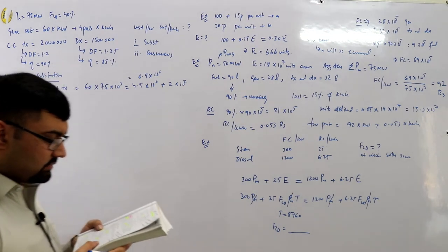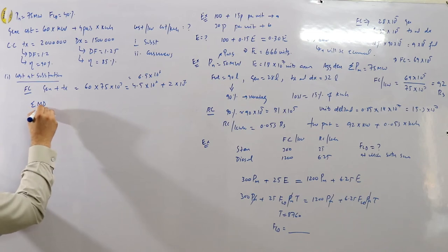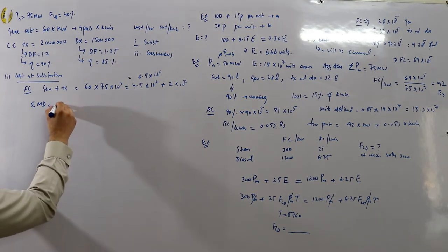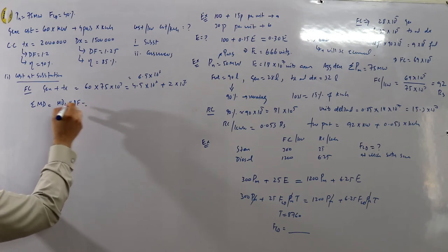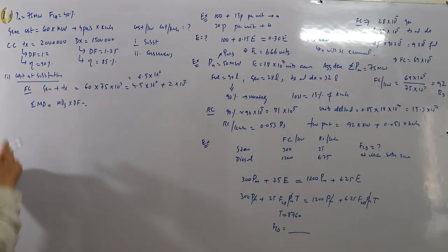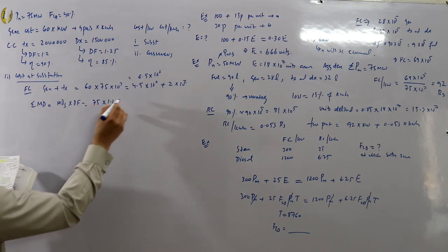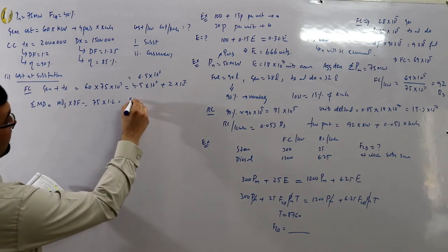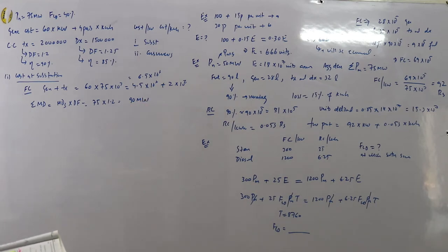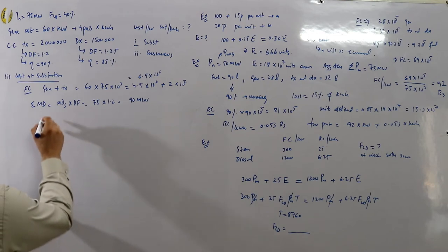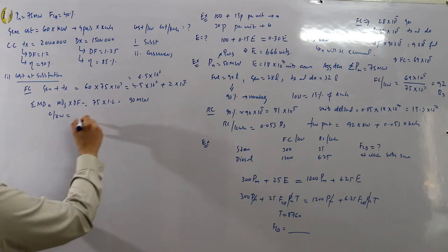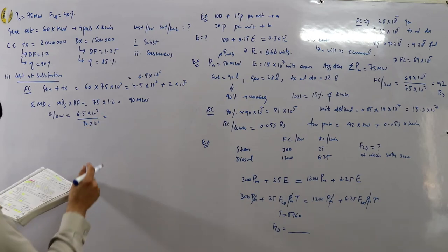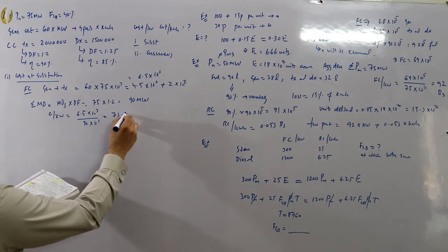Aggregate maximum demand at substation = maximum demand × diversity factor = 75 × 1.2 = 90 megawatts. Cost per kilowatt = 6.5 × 10⁶ / 90 × 10³ = rupees 72.22 per kilowatt at the substation.